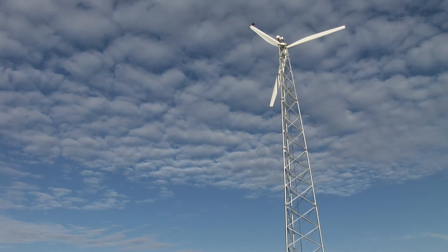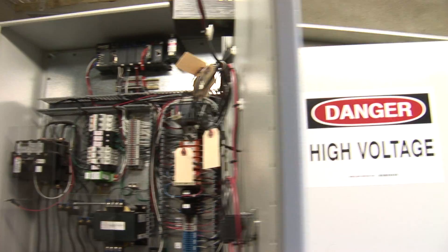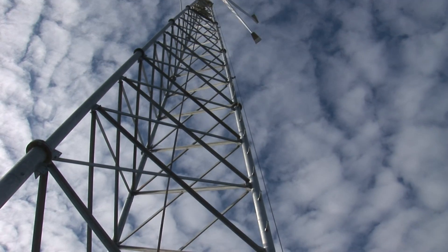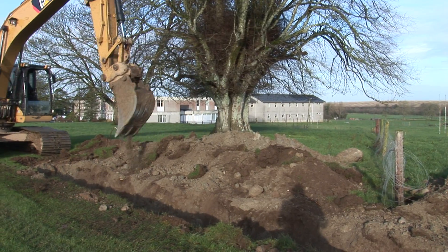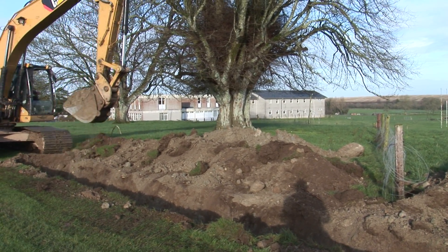This is a model customer — he's very heavy energy usage. If there is excess being produced by the turbine and the college isn't able to consume it, we can simply divert that excess through to a heating system, through immersion heaters in buffer tanks. We'll probably install a 3,000 litre buffer tank to link in with the heating system here, and that buffer tank will act as an energy store.